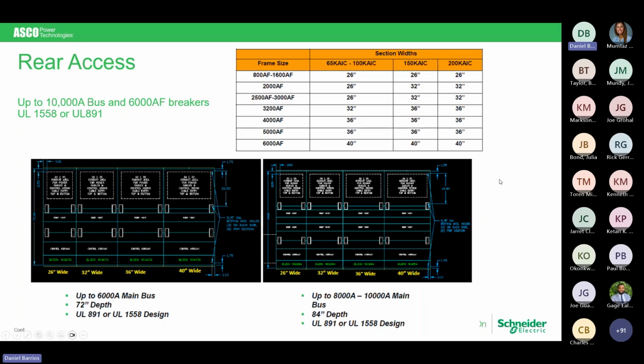The other thing I want to point out to you is that when you are laying out, and I really mean this specifically, NEMA 1, where are my conduits coming in? Are they overhead? Many times in your one-line diagrams, your single line, you show me things coming from the generators or from distribution, but I'm not really clear what you need to bring in from the top or the bottom. That's very important in medium voltage, but also something that would aid us in how we lay out sections.